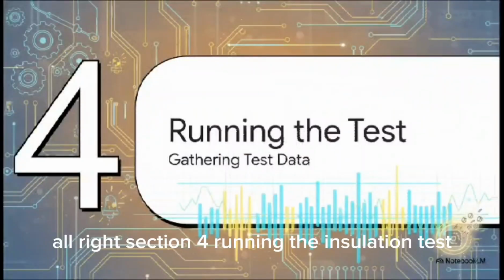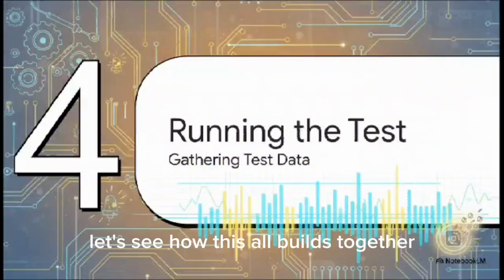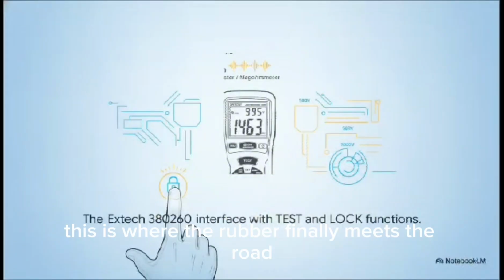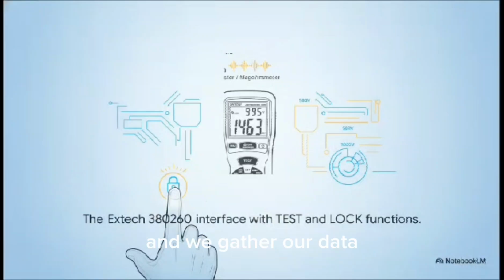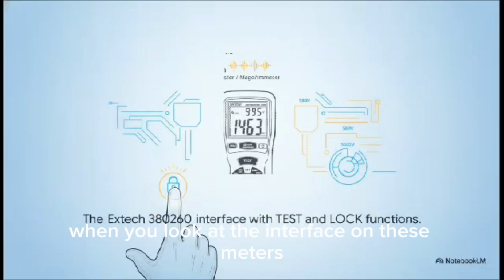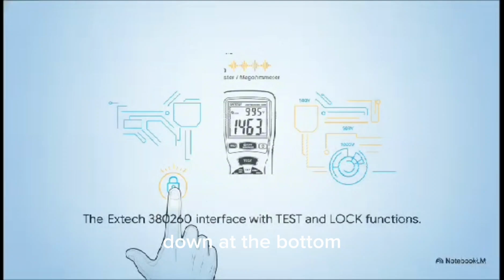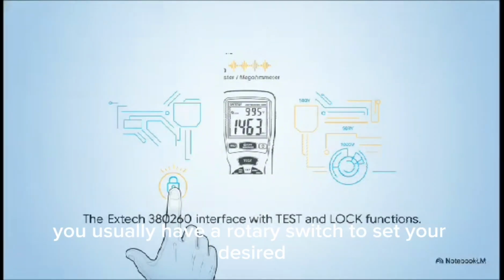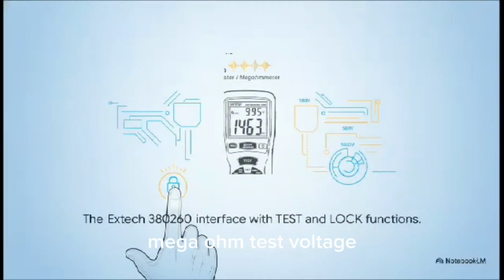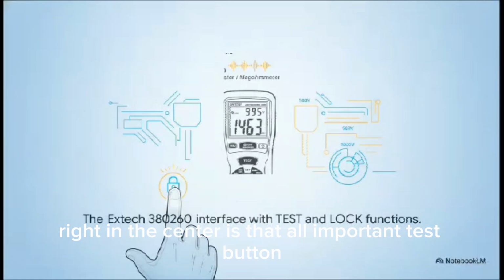All right, Section 4, running the insulation test. Let's see how this all builds together. This is where the rubber finally meets the road, and we gather our data. When you look at the interface on these meters, it's pretty straightforward. Down at the bottom, you usually have a rotary switch to set your desired megaohm test voltage. Right in the center is that all-important test button.